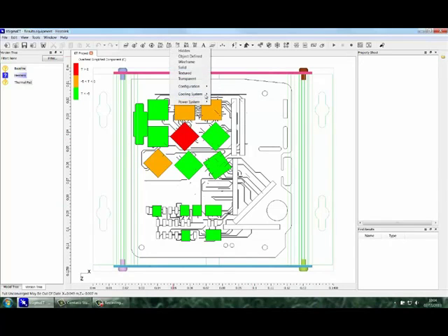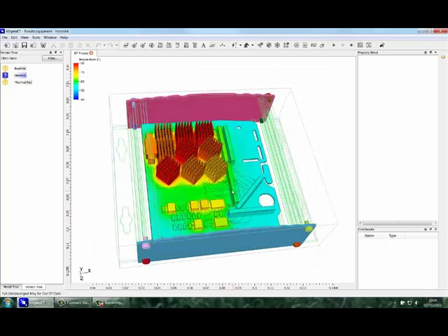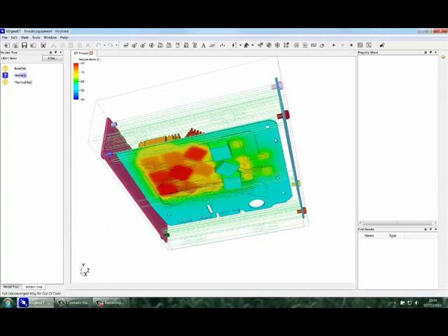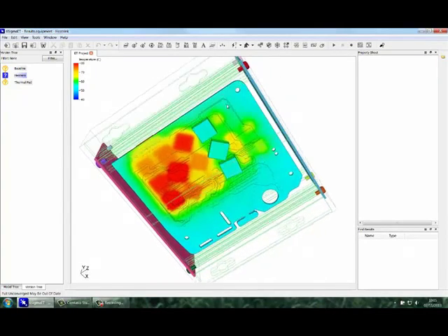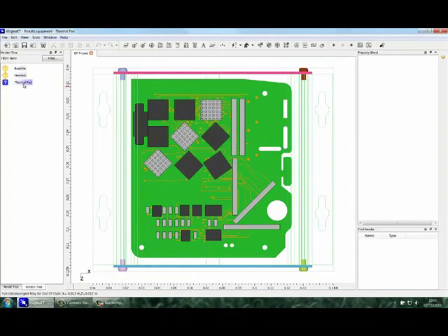If we look at the PCB surface temperature plot, we can see there's still a very hot region around the components. There are no vents in the enclosure, so there's no air entering the enclosure. Transferring the heat to the still air is not very effective, so adding additional heat sinks is not very effective. An alternative solution is to add a large thermal interface pad underneath the board.